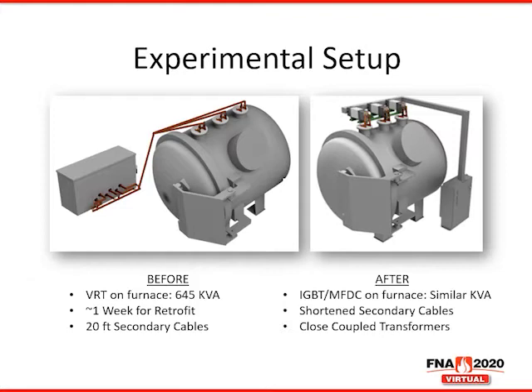So in general, we did a very good comparison of a VRT to an IGBT MFDC power control, as most elements in this retrofit didn't change. We used the same furnace, the same heating elements, so it was really a good comparison of how our power characteristics compared to the VRT.